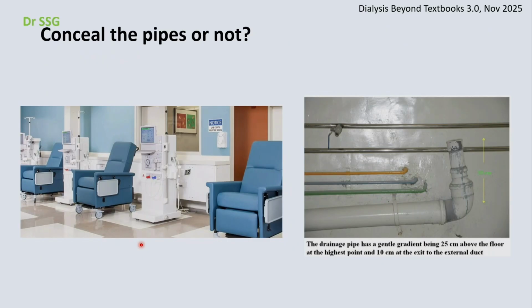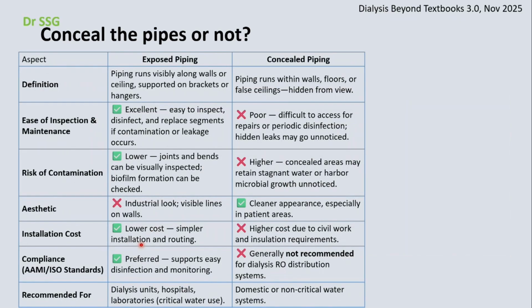So, whether to conceal the pipes or not. As sir just said a couple of minutes ago, if the pipes are concealed, we are not able to see if there is any leak, and routine maintenance, sampling ports and everything becomes difficult. It is always advisable in a dialysis unit that the pipes should be visible, wall mounted, and the drainage slope should always be maintained. Though it is less aesthetic, it is more practical and feasible. It's preferred.